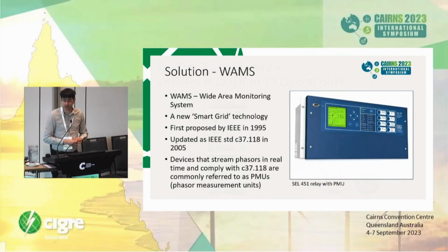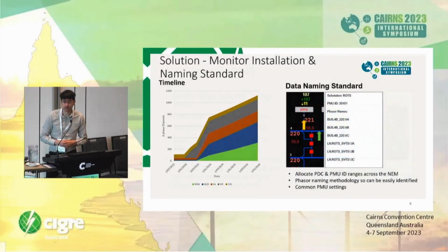So how have we tried to address it at AEMO? Well, we've started to increase our rollout of phasor measurement units, and there's a bit of information which is mostly what Mladen talked about earlier. But the main thing is that for AEMO, we're really looking at increasing our penetration of these PMUs. So we've set up a project with the NSPs to rapidly deploy as many PMUs as we can in critical areas of the network. You can see there's a diagram of our committed rollout of PMUs. We're sitting at about a couple of hundred channels at the moment, but we're expecting to roll out up to close to 1,200 channels on the system.